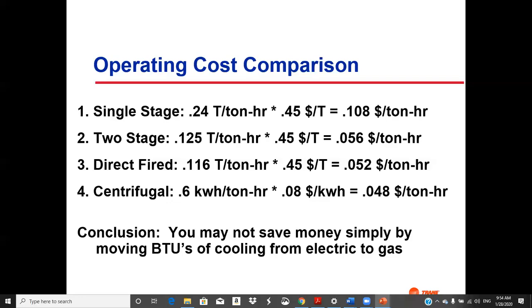We got a two-stage absorber. We got a direct fired, which would be a two-stage absorber, direct fired, and a centrifugal chiller at 0.6 kW per ton. And so you see, right now, given these two rates, $4.50 a million for gas and 8 cents a kilowatt hour, it looks like you wouldn't want to mess with this stuff. Well, where the payback sometimes comes is time of day metering, where you have on-peak periods during the day where the price of electricity is really, really high. And then you have off-peak periods where it's not nearly so high. So we're going to investigate that a little bit.